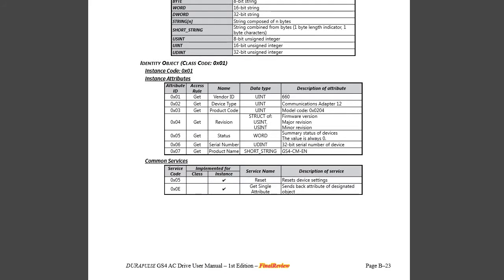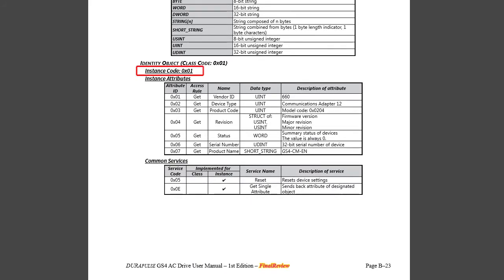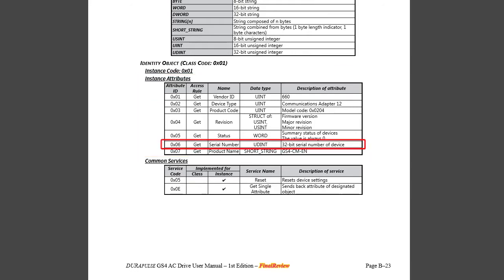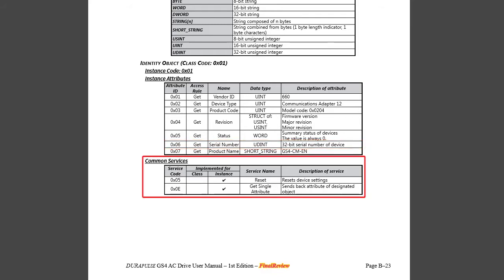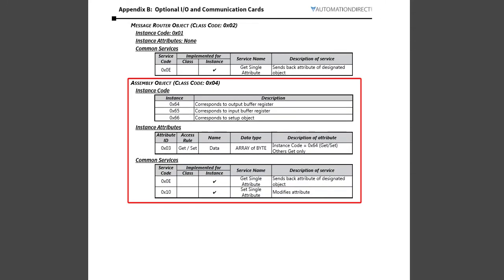If I scroll down to the identity class, I see there is one instance and it is number 1 and it has these attributes. We used attribute 6 for example, the serial number, in our example just a minute ago. This table is the services. This says we can only read and reset. There is no write ability for the identity class. Which makes sense. We wouldn't want to overwrite the serial number or the vendor ID, right? In some apps you will have to tell them which service to use. This Ethernet IP Explorer app that we are using right now does it automatically for us.